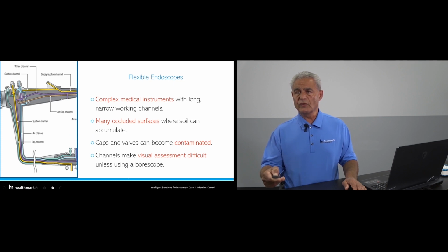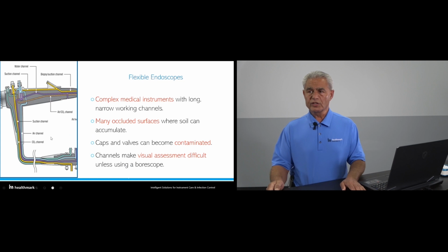Or the valve area, you have all these 90 degrees that are sometimes difficult to clean, and you need to look at the magnification or borescope to go inside this and make sure that all the debris is removed from those cannula.